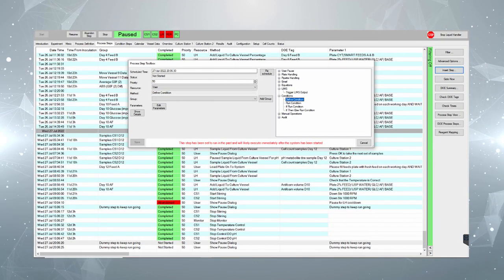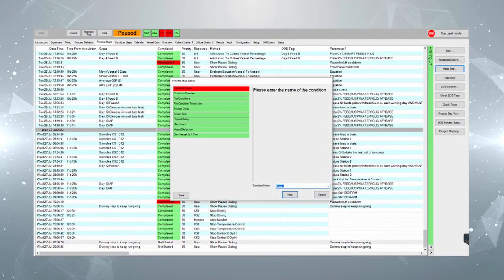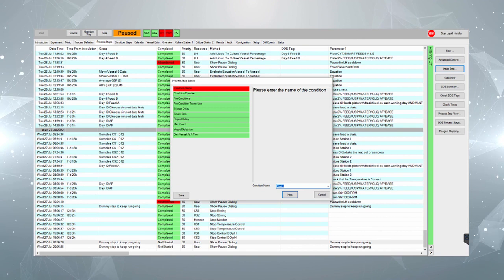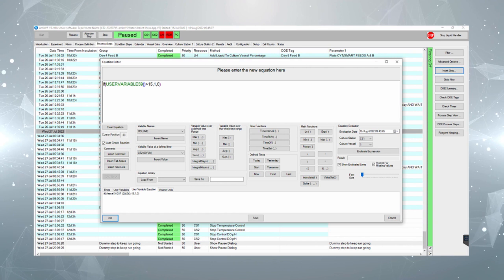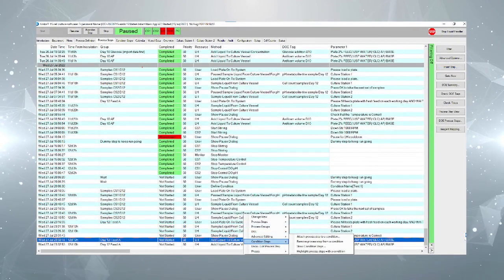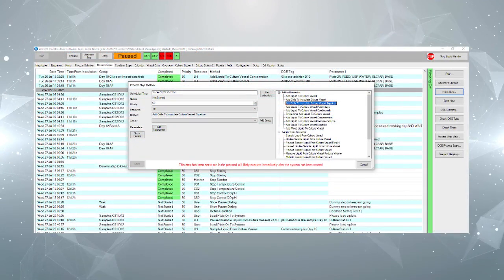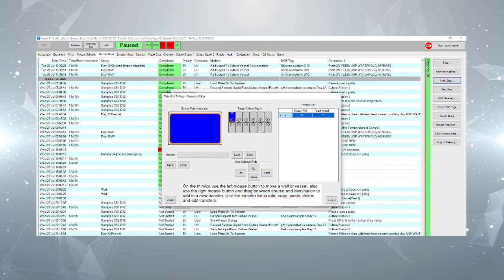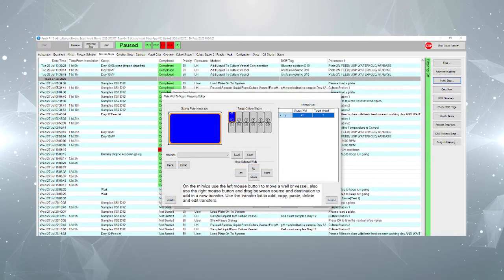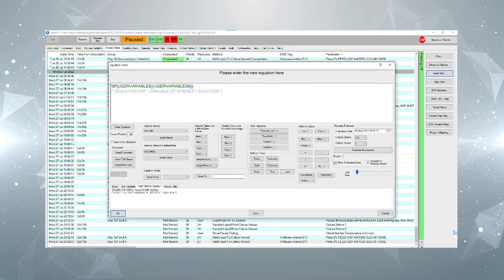So this is using the conditional steps within the AMBER control software. For example, if the LCMS results show that you have a high amount of mannose 5 in vessels 5, 6, 7 on the second station, then the AMBER 15 could follow the conditional step and add more of a particular feed to those vessels.